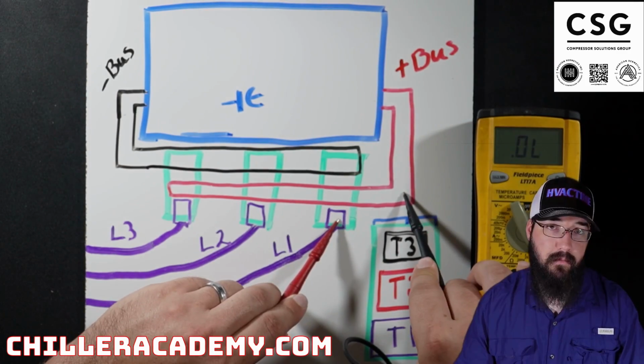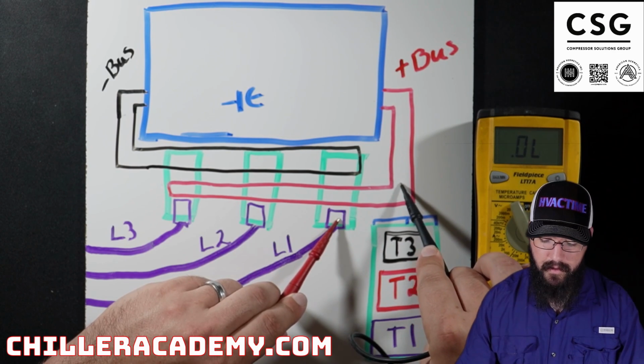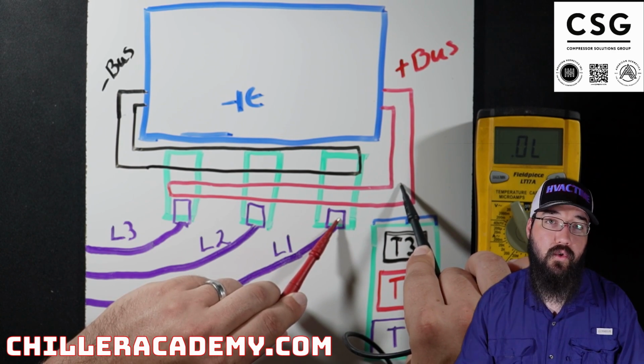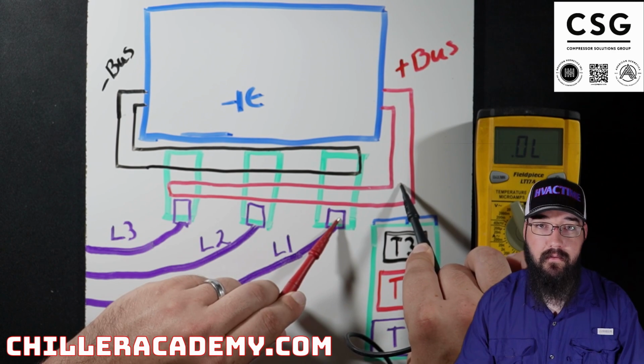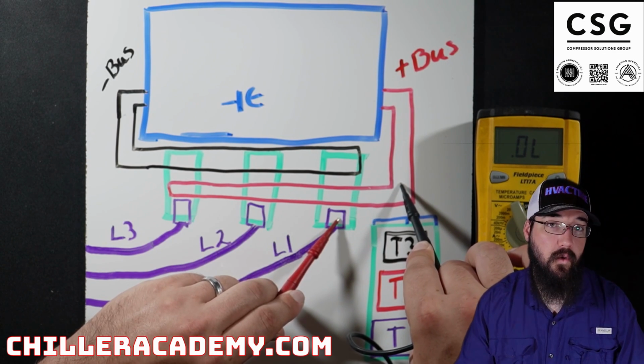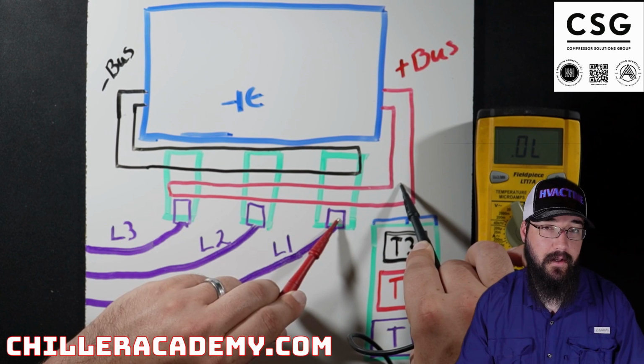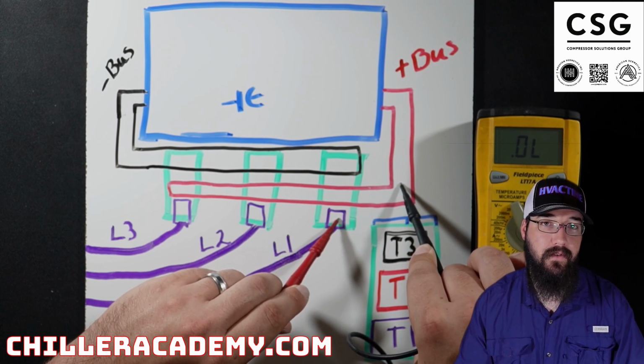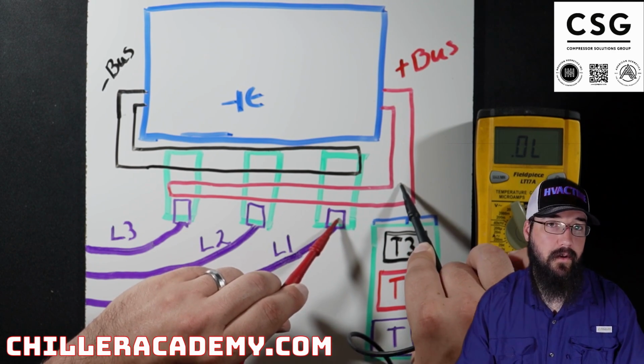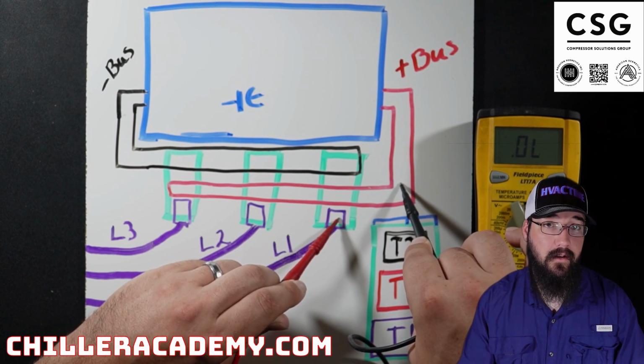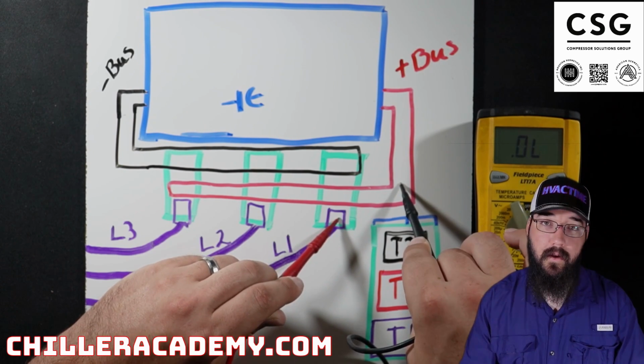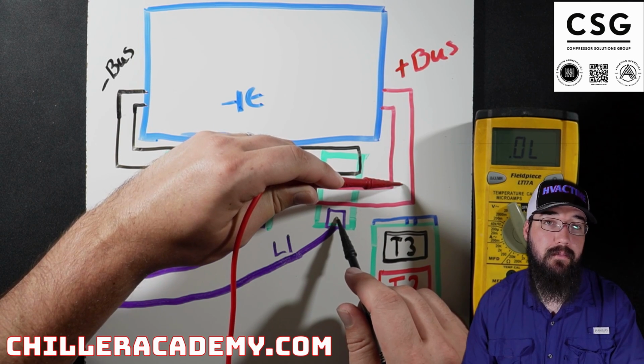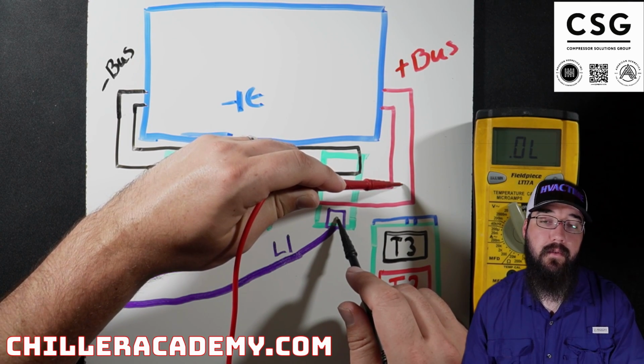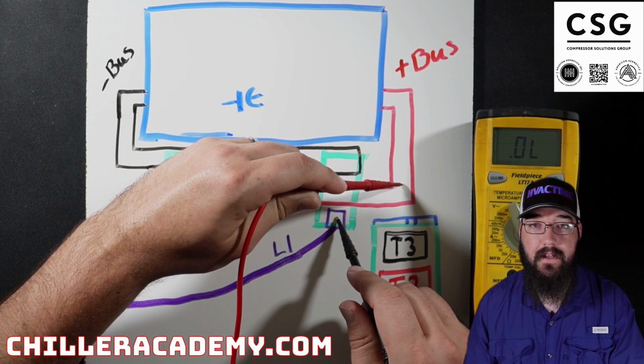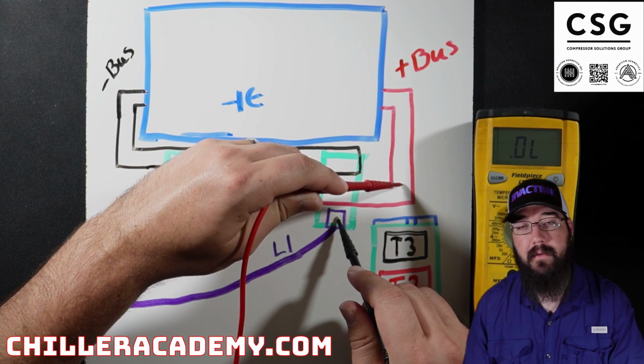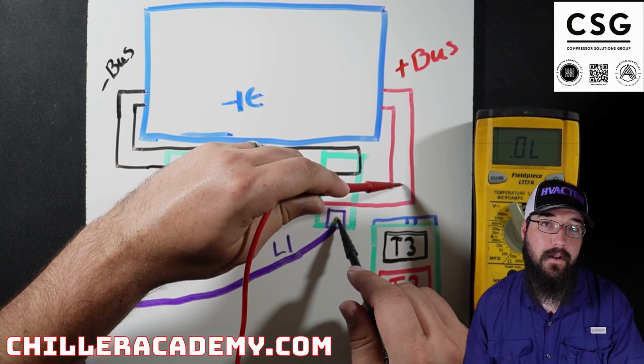So T1, with your black lead on the positive bus, you should see a 2 to 3 volt DC, or it could be an OL. Depending on, if I understand correctly, the internal orientation of the silicon, it will be one or the other. If you're using an analog, it would either be 70 ohms or OL. If you reverse your leads, it should be the other reading. So it could be 2 to 3 VDC or OL, which would be 70 ohms to infinity on an analog.